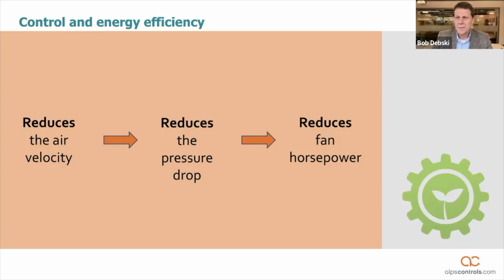We talked about this earlier. We talked about the energy efficiency issue. If you reduce the air velocity, you reduce the pressure drop, and that reduces fan horsepower. Pretty simple physics that take place in the HVAC industry. But one of the things that high level of accuracy does, it resolves many of those control issues that we've experienced, especially at low flows. And as most of you know, based upon the ASHRAE ventilation rate procedure that resets the minimum airflows based on occupancy, it's critically important to have high accuracy airflow measurement at those low velocities. That problem is solved by the smart air valve.